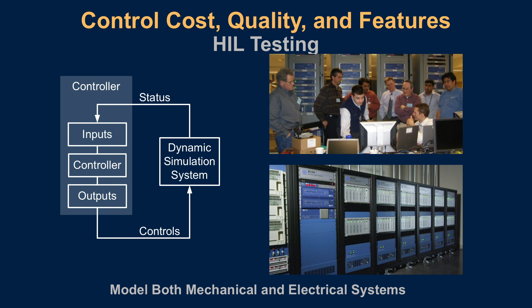In this example, a transmission power system. We also simulate the protection systems, with facsimiles of the substation or multiple substations operating as well. Those four or five racks you see in the top picture represent a substation environment operating against a simulator. From a power protection perspective, we're measuring the inputs, looking at the controller and the outputs.